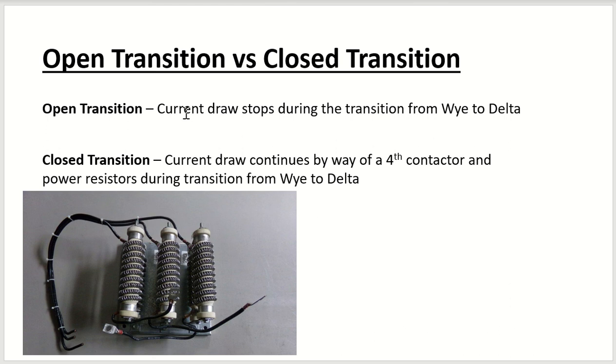That draw of current when it just stops and restarts can cause problems with the power system in a building. So they have what's called closed transition, where the current draw continues by way of a fourth contactor and these power resistors during the transition, so that you still maintain some current draw when it does the transition from Y to delta. And if you ever see these great big resistors, these are high wattage, low resistance resistors. This is just for that short period of time when you transition from the Y to the delta, and this through the motor windings keeps a load on the power system as it transitions.